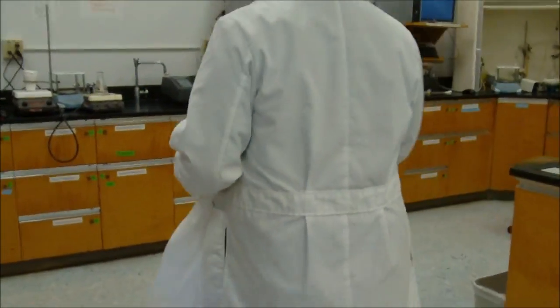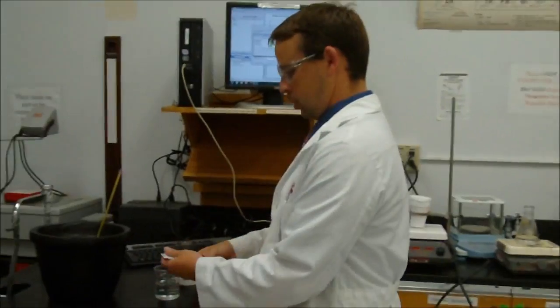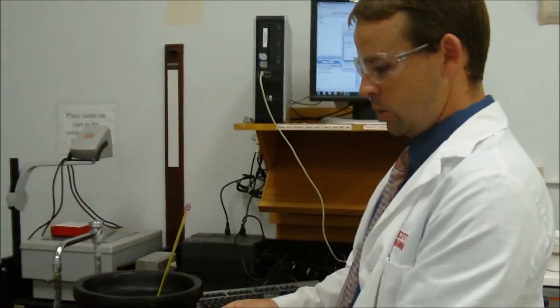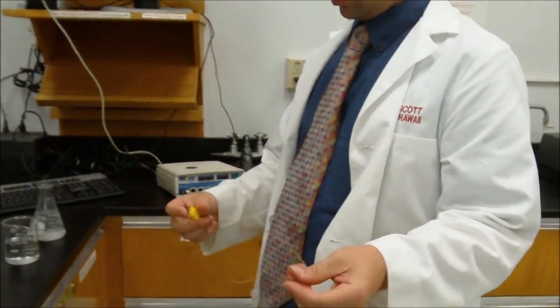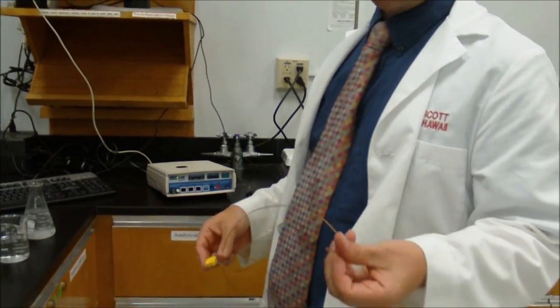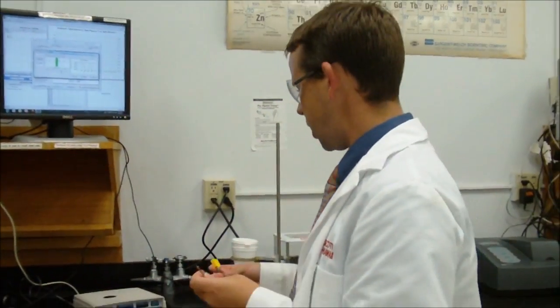Okay, we take the thermocouple out. The thermocouple is a wire that has two metals, and the junction of those two metals creates a voltage when we connect those two metals together, and that voltage is dependent on the temperature. So as the voltage changes in the wire, then you can identify what the temperature is, right?